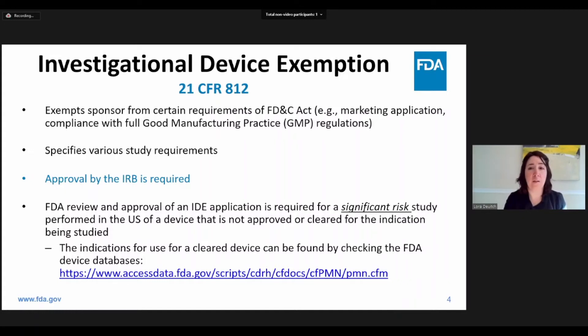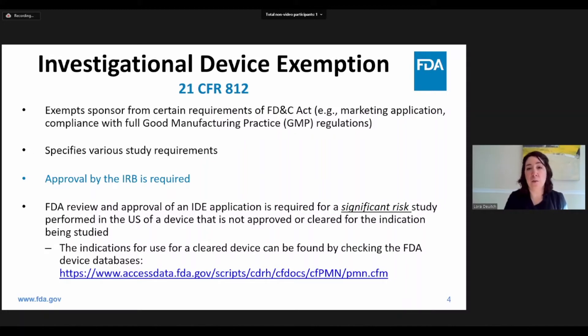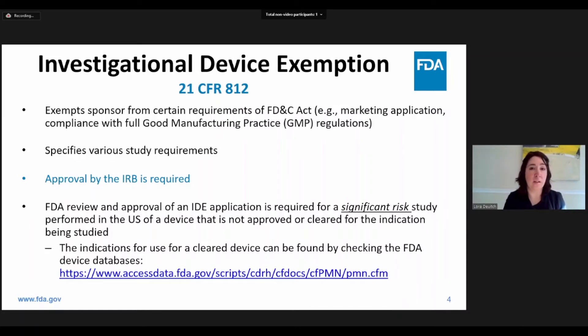IDE regulations can be found in 21 CFR 812. An approved IDE application permits a device that otherwise would be required to have FDA clearance or approval before use to be used in a clinical trial, and exempts sponsors from certain provisions of the Food, Drug, and Cosmetic Act, such as compliance with full good manufacturing practice regulations. At a high level, FDA review and approval of an IDE application is required for a significant risk study performed in the US on human subjects when that device has not been cleared or approved by the FDA for the indication for which it is being studied.